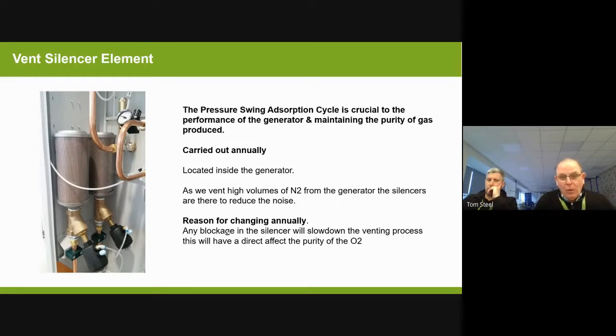If this silencer gets blocked at all, then when the system goes to depressurize, it will depressurize slowly. We want this to depressurize very, very quickly. By depressurizing very quickly, you flush out all the N2 that's in there. If for any reason there's a blockage, and even if we reduce that depressurization by a few seconds, you are going to have problems with your purity. So indirectly, the silencer has an effect on the purity of the gas that you're going to produce.